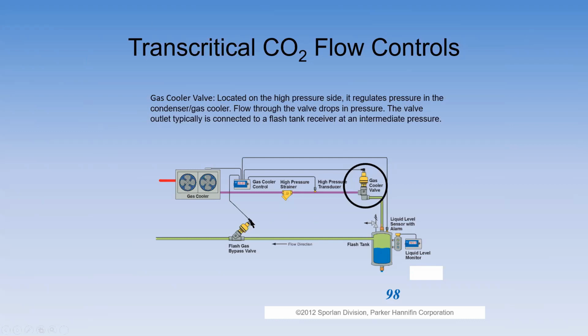So that's where this valve and this tank come into consideration, to make it get back down to CO2, which is 100% liquid. I have to play games with the temperature and the pressure. So this is more than a head pressure valve, I'm controlling what's happening on the drop leg. You with me on this?